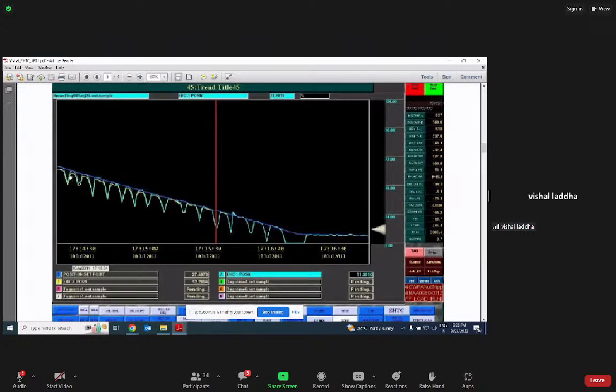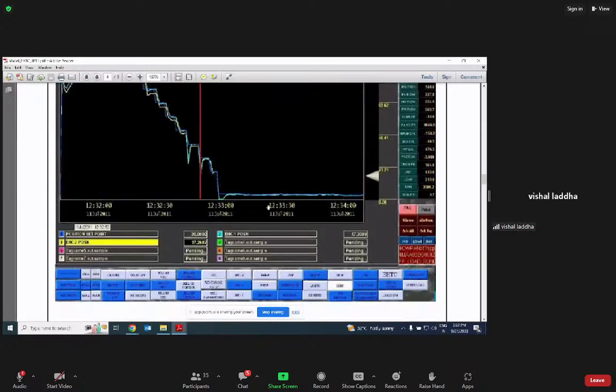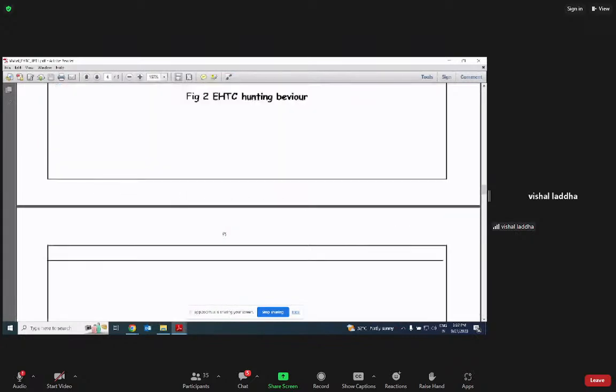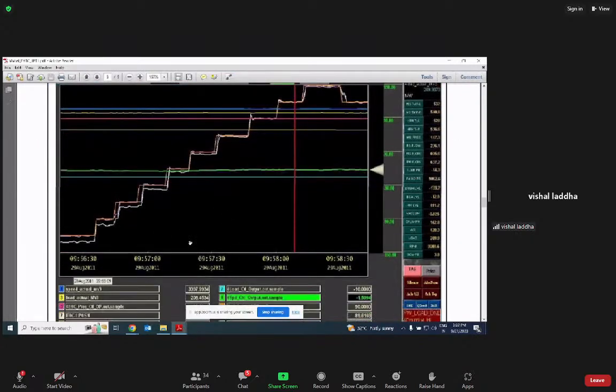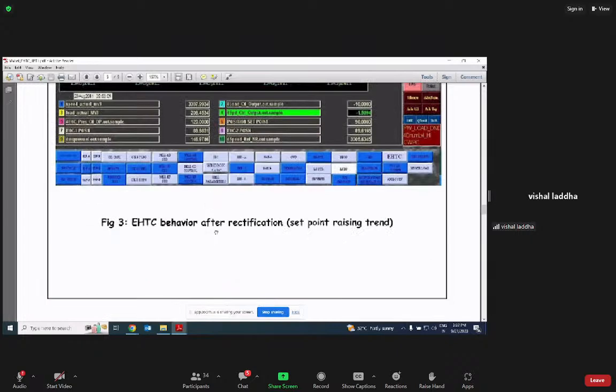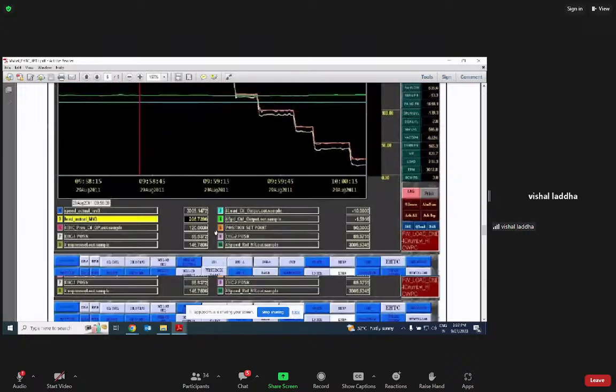In this situation you can see the blue line is the position set point, but the EHTC position is continuously hunting. Then after the work was done, you can see both trends are at the same place. This is the EHTC position and the EHTC commands, and now the command is following load control output and speed control output. Everything is following, and this is the EHTC behavior after rectification with set point raised.